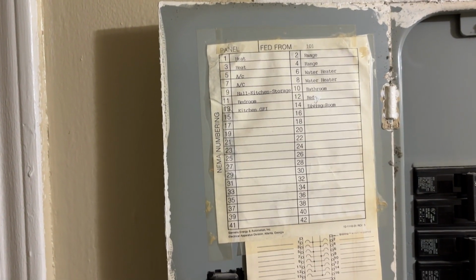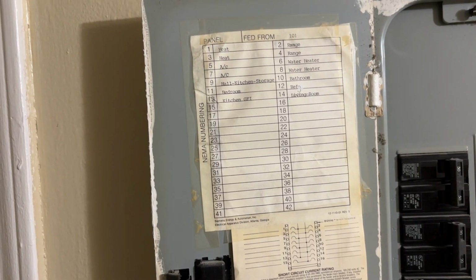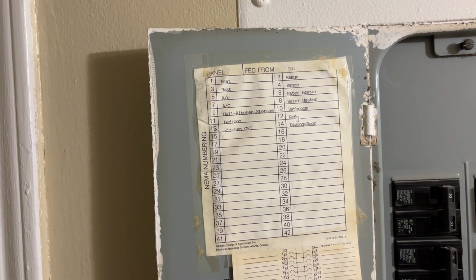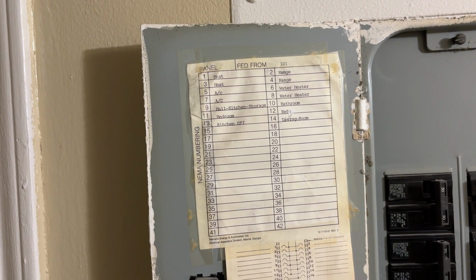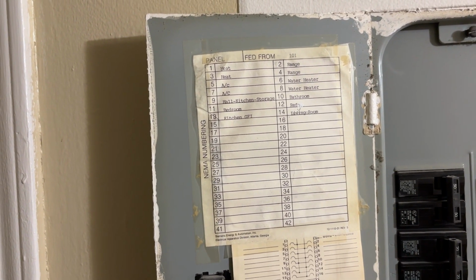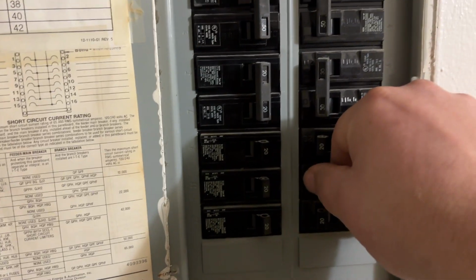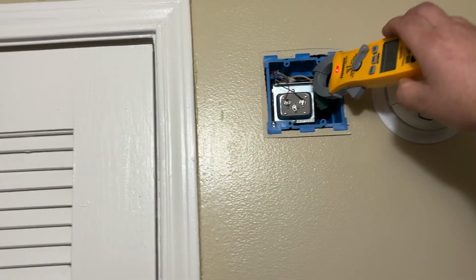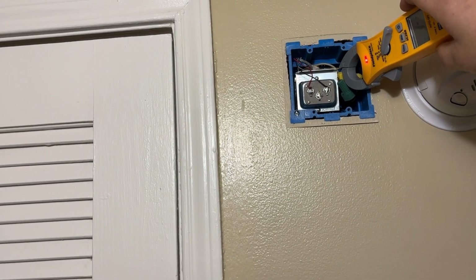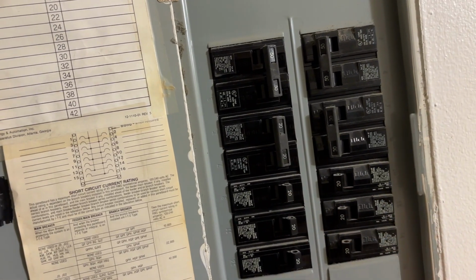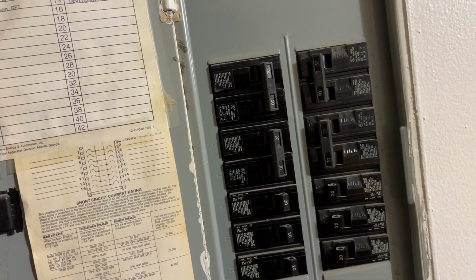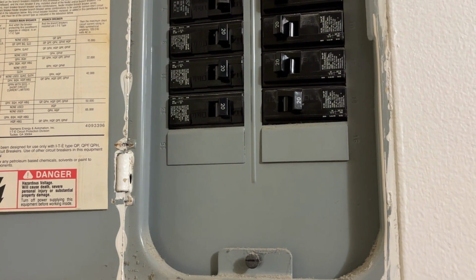Come to your breaker panel to see if you have a label. This one does not have one that is marked for the emergency pull cords. So we would start with our 20s one at a time. We would cut a 20 off. And we would go back and we see that we still have power. We would continue this until we find out which breaker it is. We can cut this breaker back on. We can go in a set order so we don't get confused. Once the proper breaker is located, we can leave this off for now.